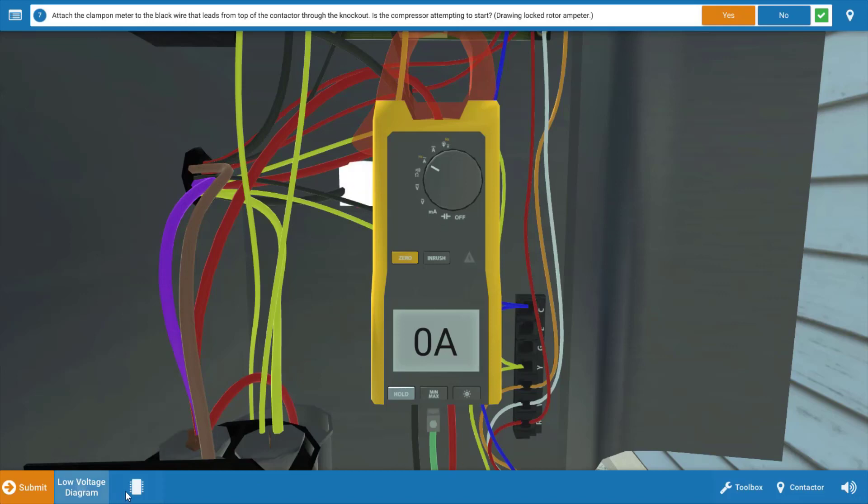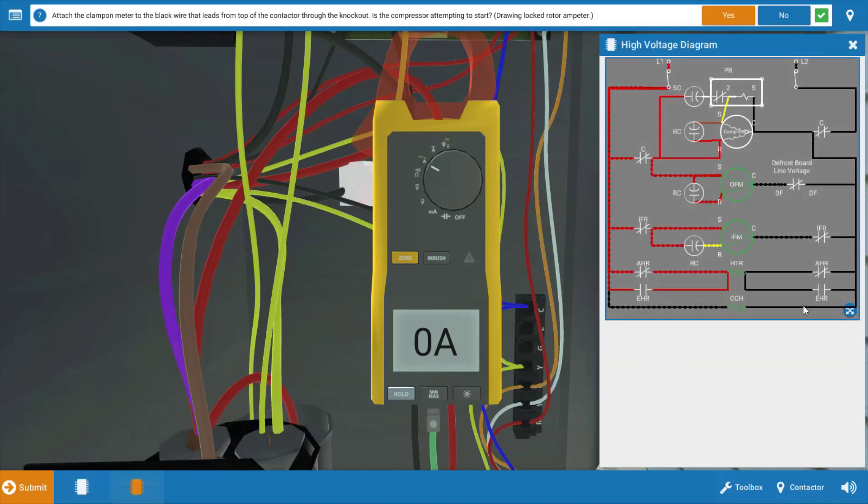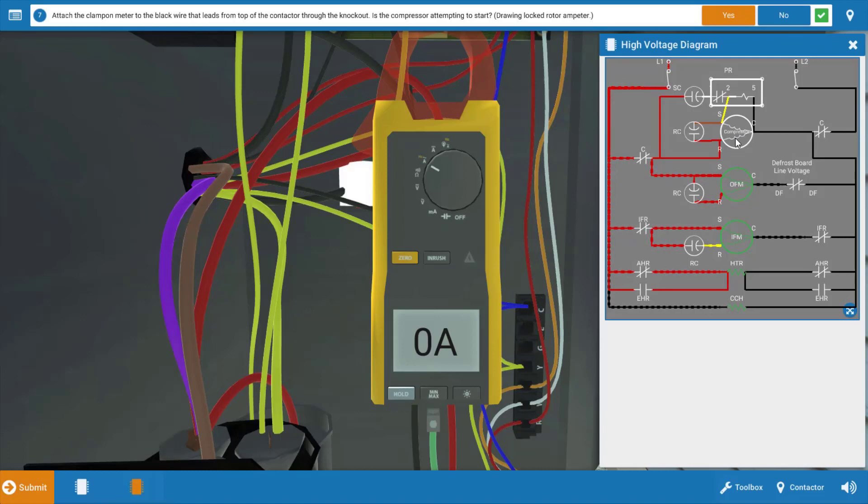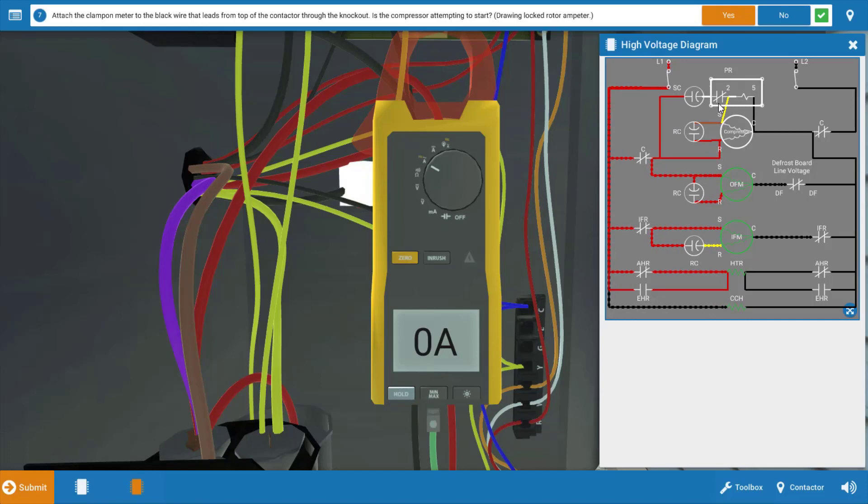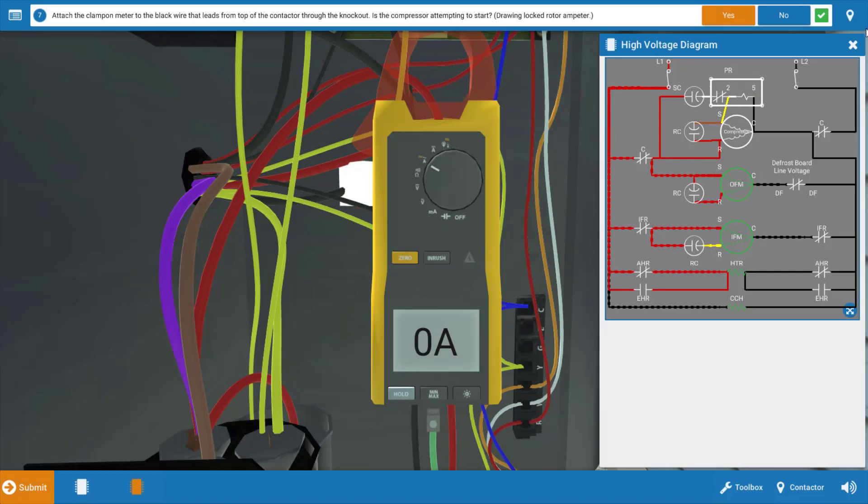Now, for one, let's look at the wiring diagram. It's possible that we have an open winding in the compressor, but it's also possible that either one of the capacitors is faulty or we have a set of potential relay contacts that are faulty. All of these devices are in series to the start winding. So we're armed with four possible causes: the compressor motor, the start capacitor, the run capacitor, or the potential relay.